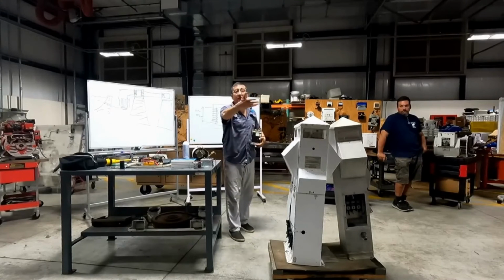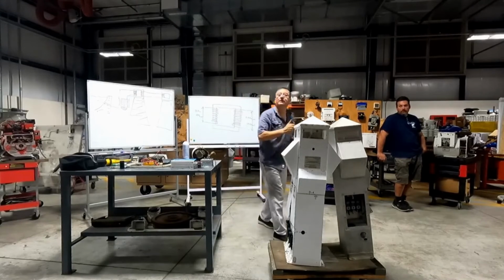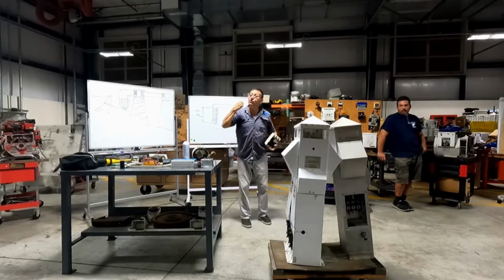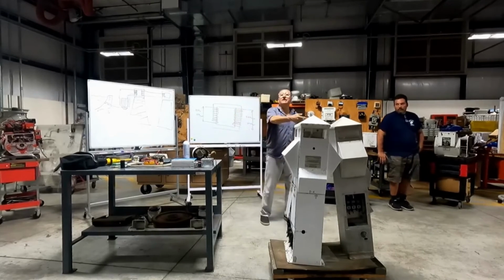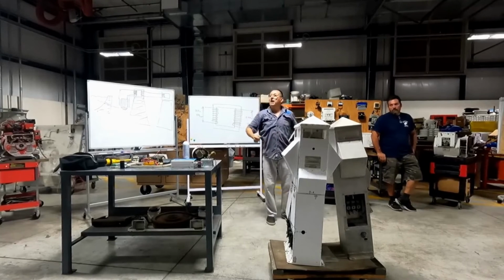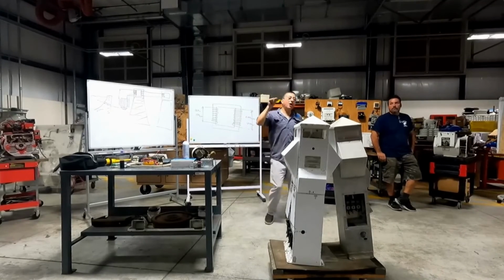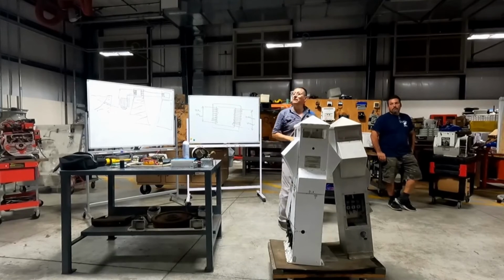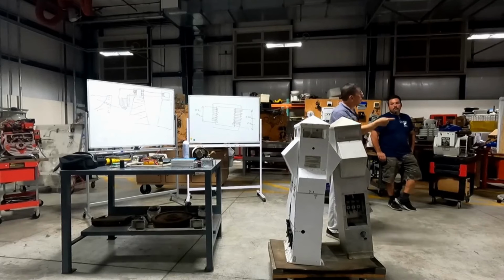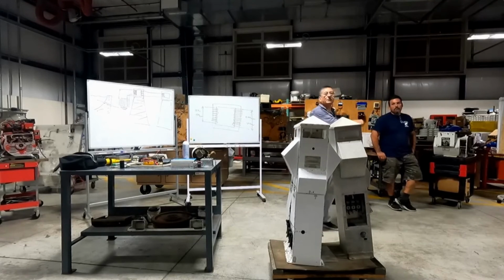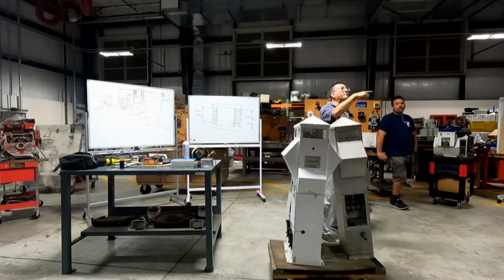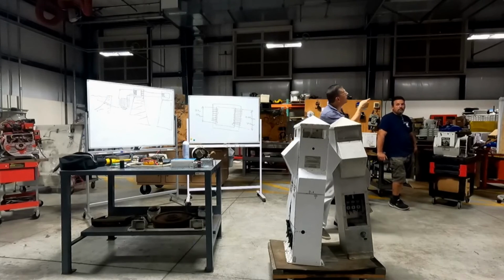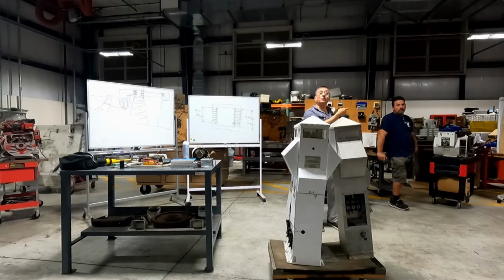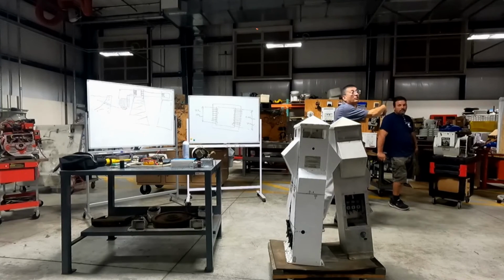This is constant in all the marinas. In the future, you will be the engineers in a marina and you will need to respond for the pedestals. Because the customer is calling the office, hey, I don't know what happened with your pedestal. My air conditioning pops the breaker every 10 minutes. It's a problem with your power. And you go to the pedestal and you demonstrate to them, no, Mr. Bless, the problem is not in the power of the marina. The power here is perfect. You have a problem in your boat. Can I enter your boat and demonstrate that you have a problem in your air conditioning equipment? Oh yeah, go ahead. And you demonstrate to them.